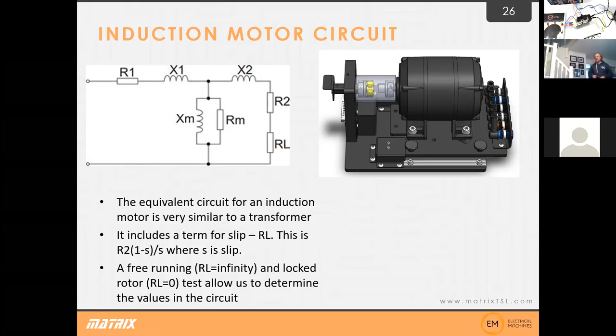For that, we have an add-on called the locked rotor add-on, which is basically just a three-phase induction motor. You're able to either get the rotor to be free running or physically clamped down. It plugs into the control box, and allows you to measure the voltages, currents and phase in those two circumstances, so you can come up with a model for the equivalent circuit.